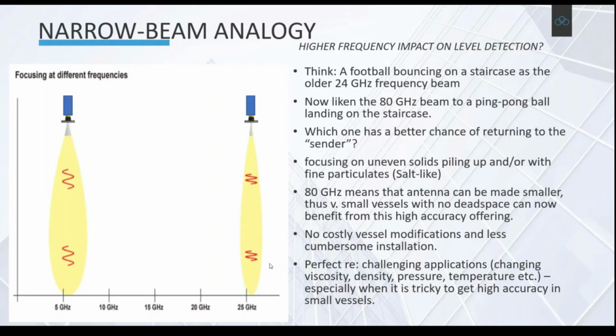But that ping pong ball, which is the 80 gigahertz, that will probably pop back up to sender. So they're smaller wavelength, they hit surfaces, uneven solids, low reflective media. This has a chance of, because it's small, it fits within that, at the micro level, and it will hit back to your sending point. And obviously it's a central point - the radar is fixed, it can only receive at these points. So smaller wavelength means it will come back to sender.